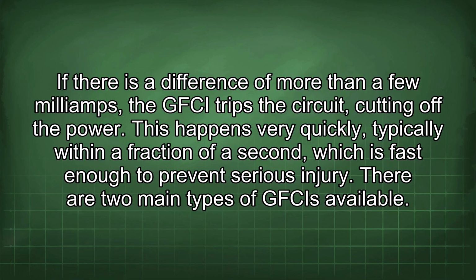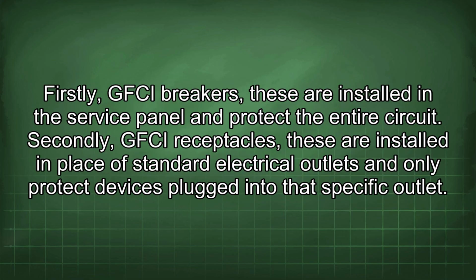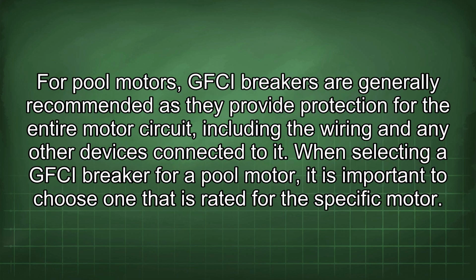There are 2 main types of GFCIs available. Firstly, GFCI breakers. These are installed in the service panel and protect the entire circuit. Secondly, GFCI receptacles. These are installed in place of standard electrical outlets and only protect devices plugged into that specific outlet. For pool motors, GFCI breakers are generally recommended as they provide protection for the entire motor circuit, including the wiring and any other devices connected to it.